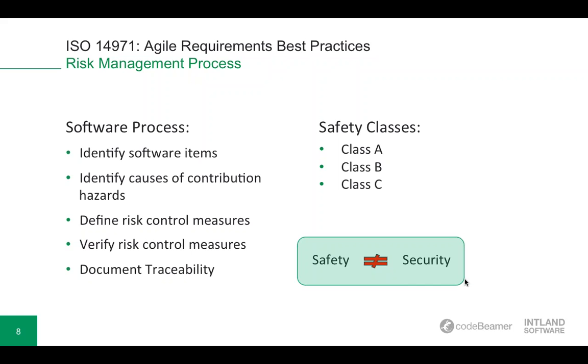So let's talk a bit about documentation. The risk management file, for example. You need to establish a risk management file for each of your medical devices. These risk management files should include all of the records and documents that your risk management process generates. They should contain risk management plans and are used to record risk analyses, risk evaluations, risk control measures, and residual risk evaluations.